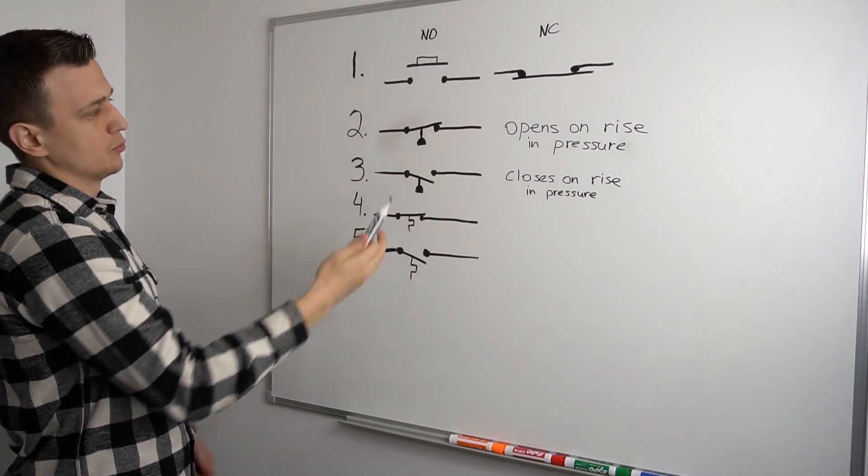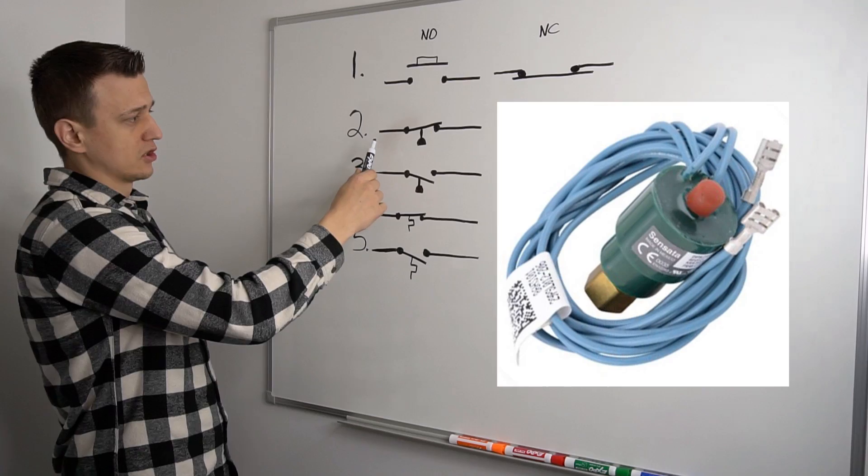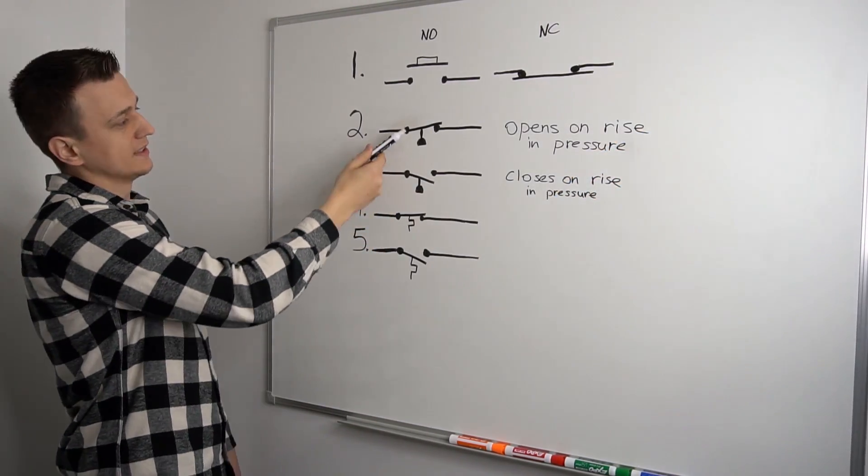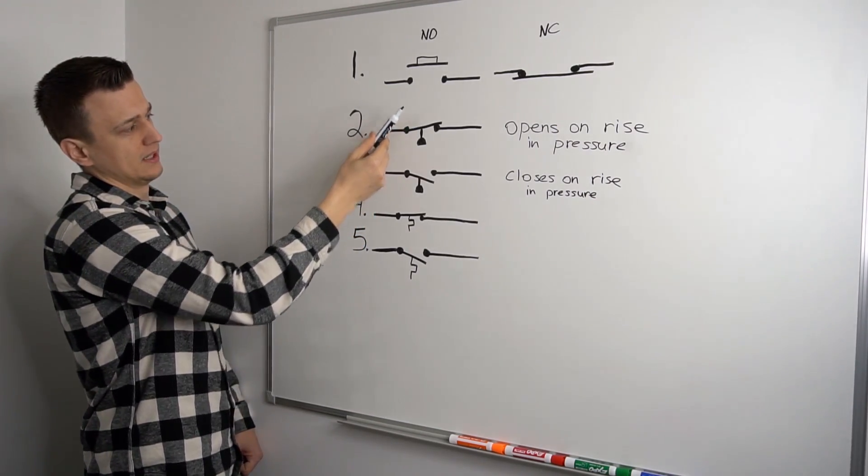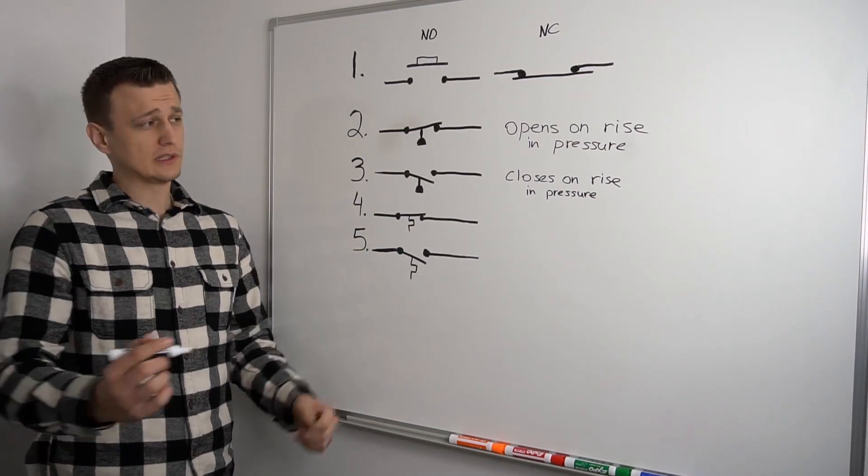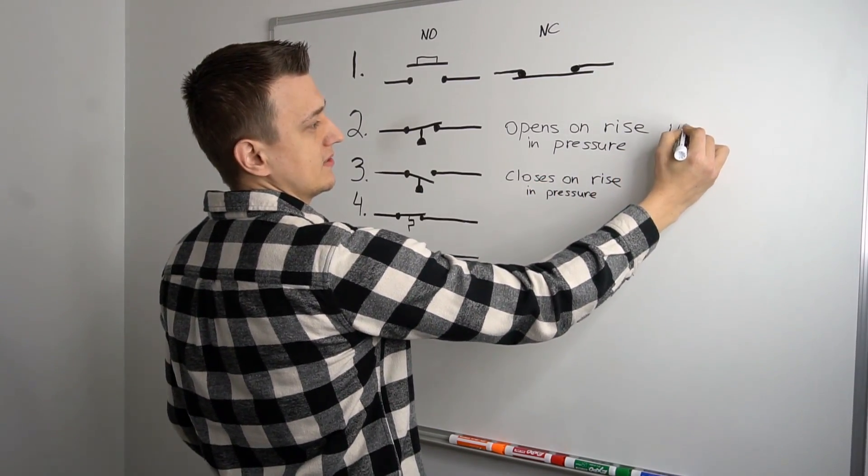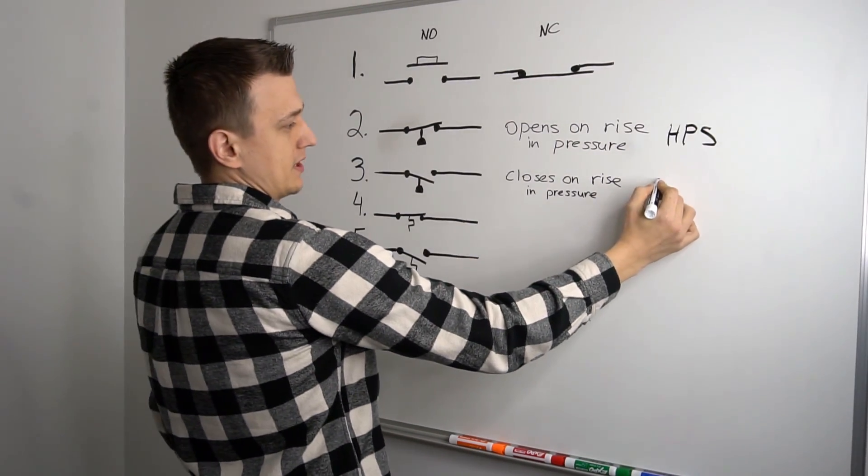This one, for example, would be a high pressure switch. So like an air conditioner. So if the air conditioner pressures, the refrigerant pressures get too high, this pressure switch would sense the increase in pressure and open up and interrupt power turning off the unit. So let's go ahead and write that down as well.